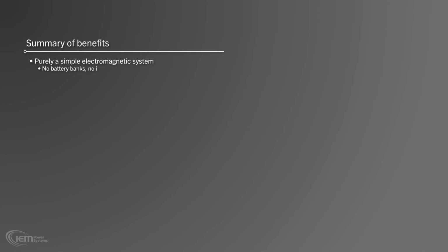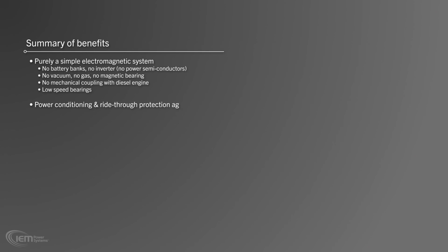Summary of benefits. Rotobloc UPS is purely a simple electromagnetic system without battery banks or inverters and with no power semiconductors. Rotobloc does not require a vacuum, gas, or magnetic bearings. Our system has no mechanical coupling with the diesel engine and employs low-speed bearings for the greatest reliability.